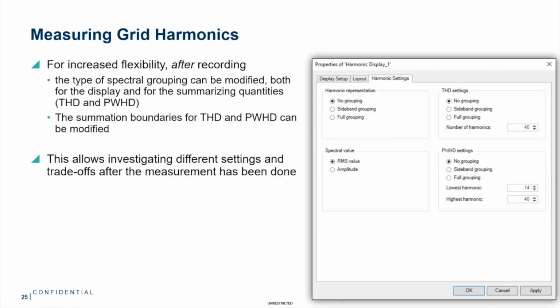One nice feature, I think, is that you can see all those signals in real time. And if you see those signals in real time, you will probably have made a choice. For example, I want to have the harmonics calculated using full grouping. And that is fine, and then you immediately see the result of full grouping. But after you have finished your recording, you can reprocess the signal, so you don't have to redo your recording. You can reprocess your signals based, for example, on no grouping or on sideband grouping. That is true for the bar charts and the tables that you see.